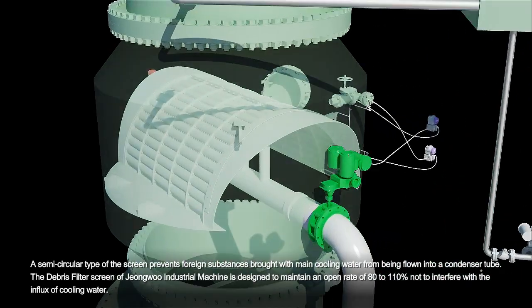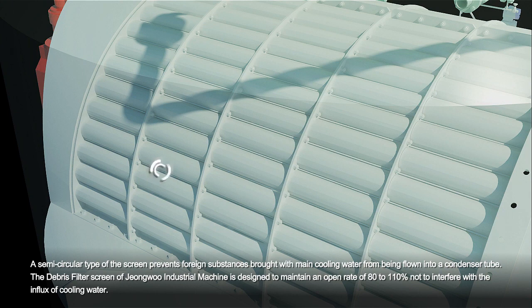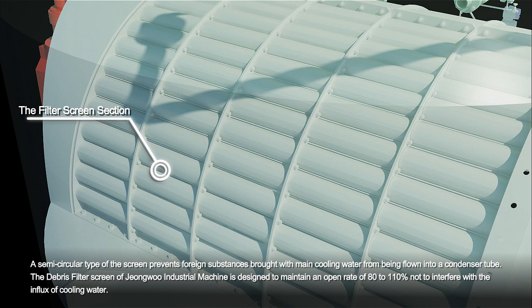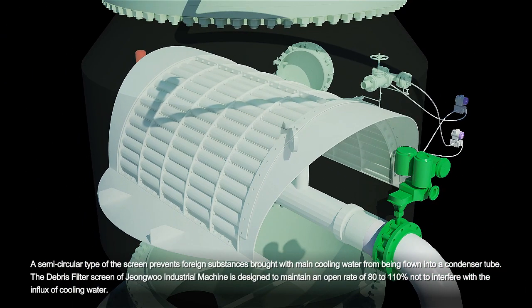A semicircular type of screen prevents foreign substances brought with main cooling water from being flown into a condenser tube. The debris filter screen of Jeongwoo Industrial Machine is designed to maintain an open rate of 80 to 110 percent, not to interfere with the influx of cooling water.